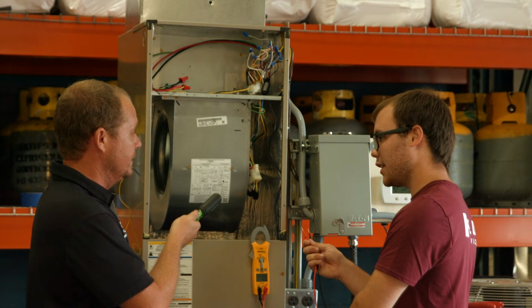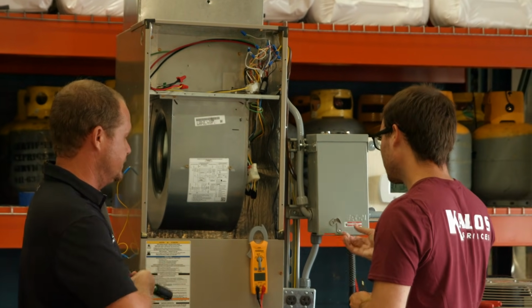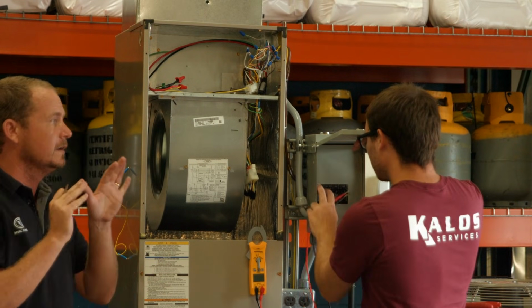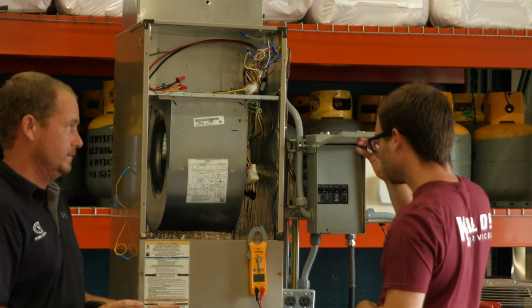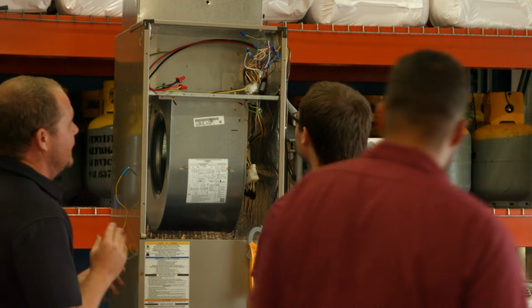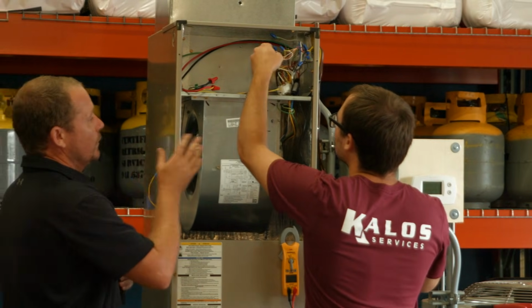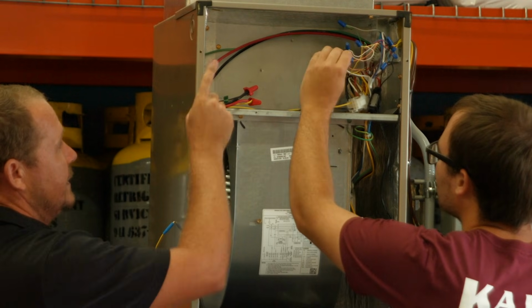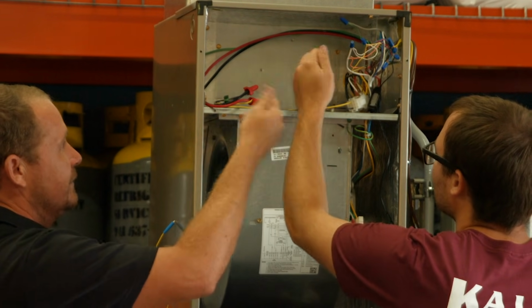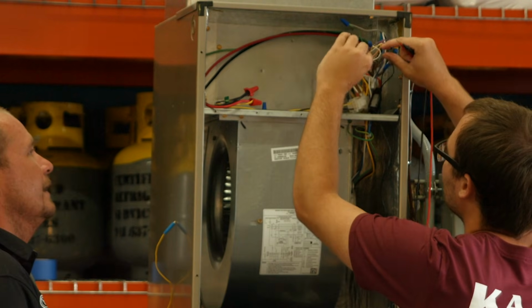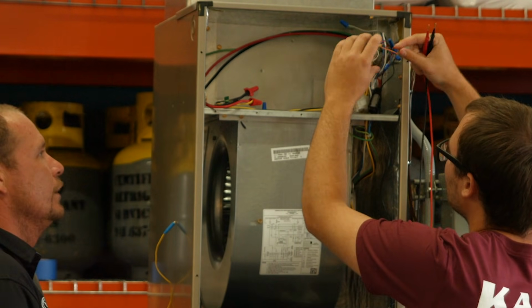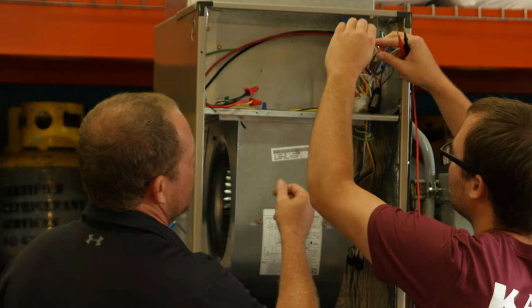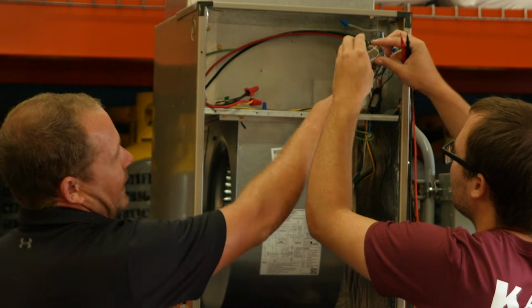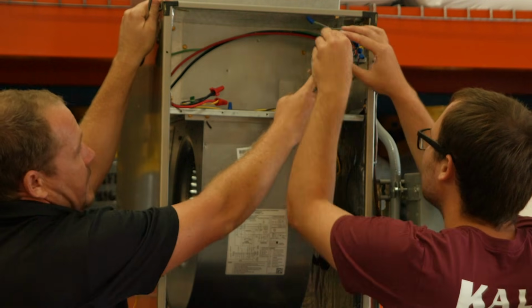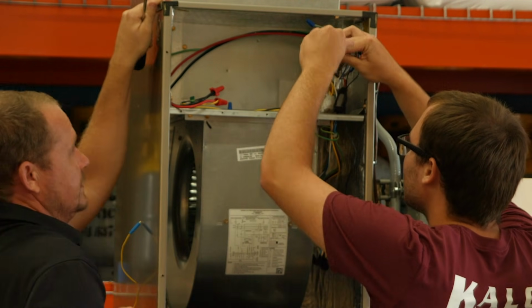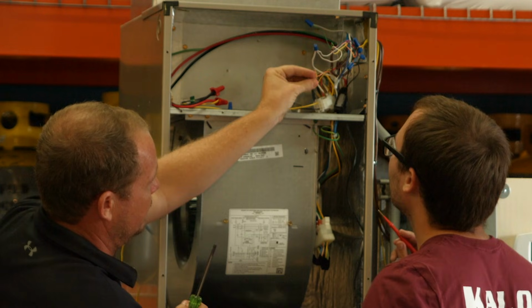All right, so now we're going to use an ohm meter. So power it down. You always only connect an ohm meter to a de-energized circuit. So it's de-energized, and we can do it on either side, but you're going to take your orange and connect it to a different color on that same cable. Ideally you would connect it to one that you know is working. I knew this one was working. But right now you're connecting to the one going to the thermostat, so make sure you're using the conductor that's actually going to the condenser. So we're just going to connect these two together.